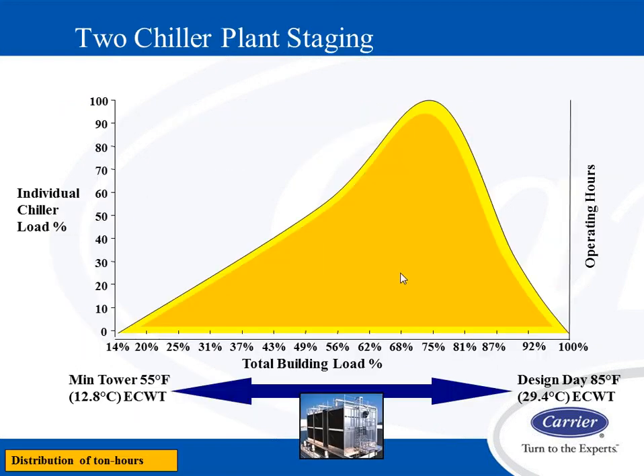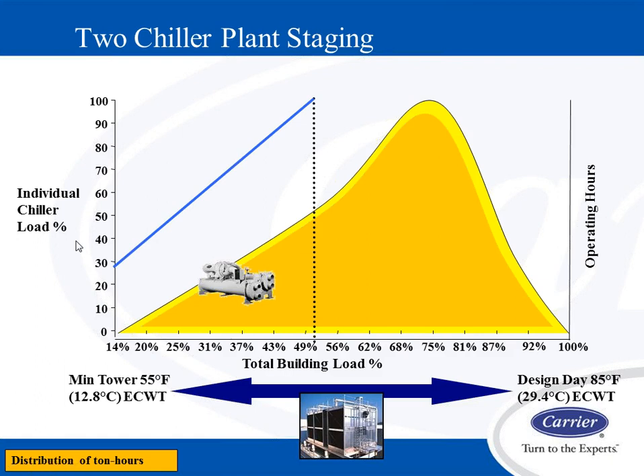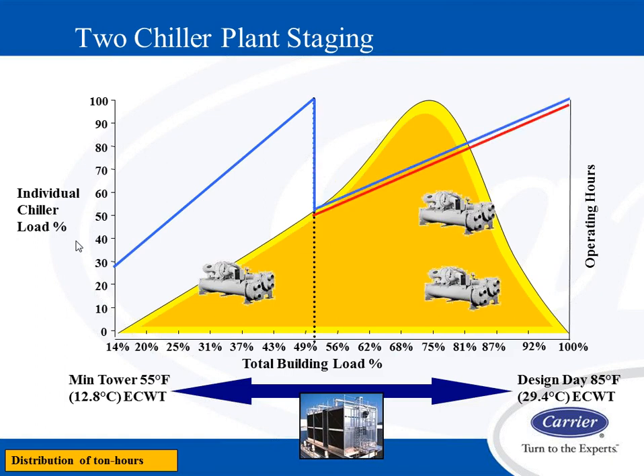If we look at a 2-chiller plant, let's say I have a minimum tower water of 55 here, and I have a design day of 85 degree entering condenser water here, and this is percent load of chiller. So I'm going to load up the chiller plant. I'm going to start up and load up my one machine up to 100% load, and then I'm going to turn on the second machine at 50% load and ramp up those 2 machines to handle the remainder load of the building.